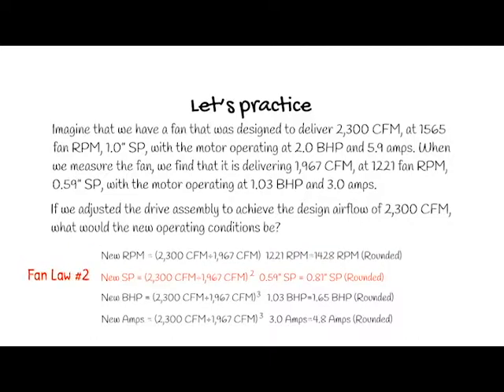Next, we looked at static pressure. For static pressure, we had to use fan law 2. Again, we took 2,300 CFM divided by 1,967 CFM, and then we squared it. We took that number and multiplied it by the original static pressure of 0.59, which gives us 0.81 static pressure.